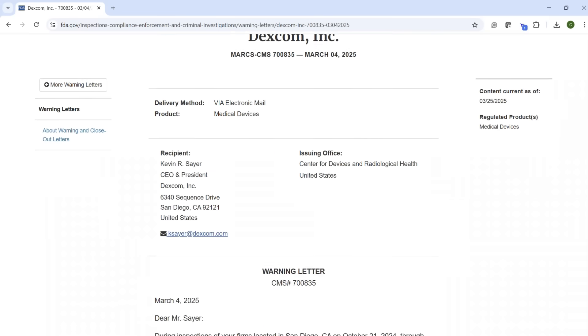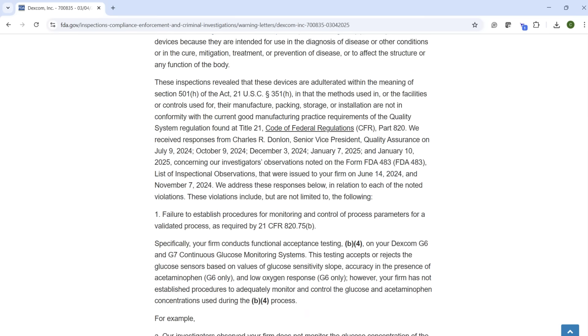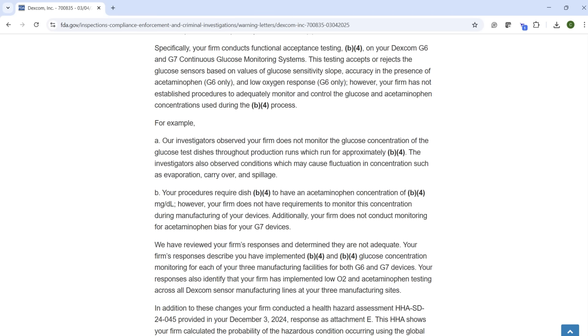I know I'm not the only one who's had some accuracy issues this year. The reason why some of us have had issues with inaccurate sensors lately could be that Dexcom, per the March 2025 FDA warning letter, had made a design change to the sensor's internal components that could reduce accuracy. It wasn't bad enough to be a recall, but Dexcom did cease the distribution of the Dexcom G7 sensors that had the material change, and they also reverted their manufacturing back to what it was before.